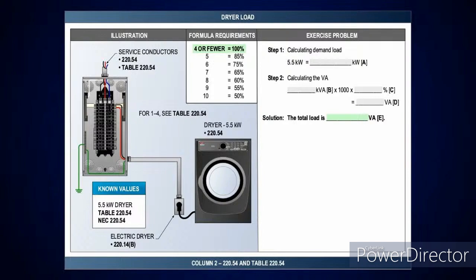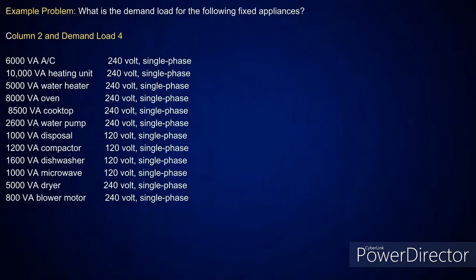All right. So this in here is 5.5 kW. That's 5,500 VA. You take that at what? 100%. Everybody should be able to do that calculation with no problem. It's only one. It's 4 or less, so you take it at 100%. And to even help you, right there in the middle of the illustration where it says formula requirements, we even have the percentages there for you to look at. All right. Now, there'll be only one other load I'm going to remove from this, but I'm going to go ahead and show now how to do the fixed appliance.